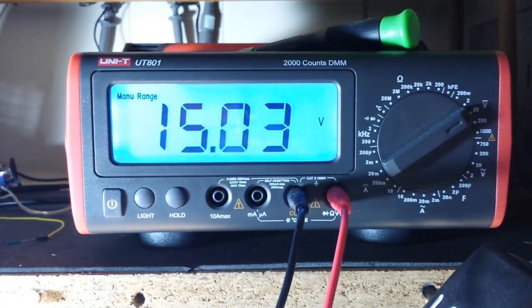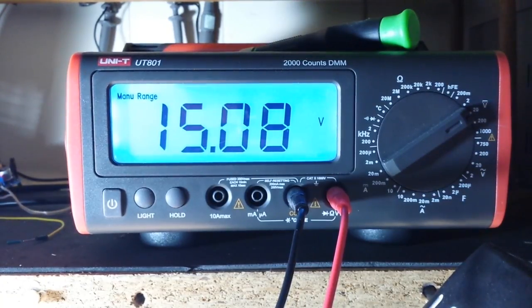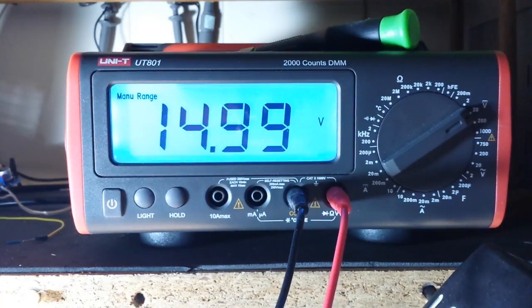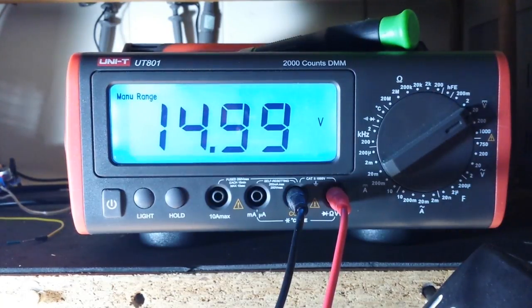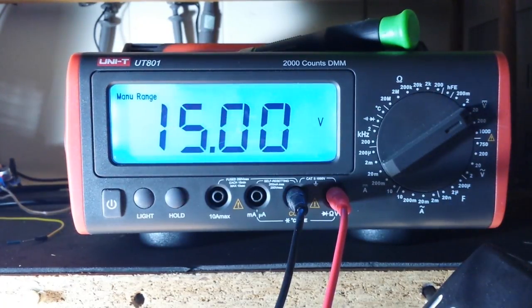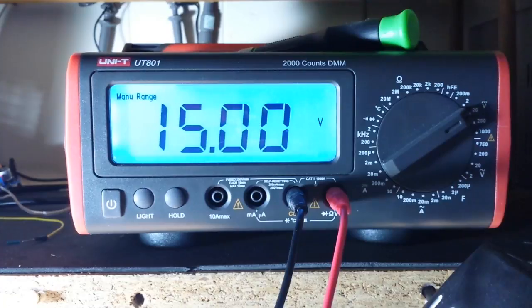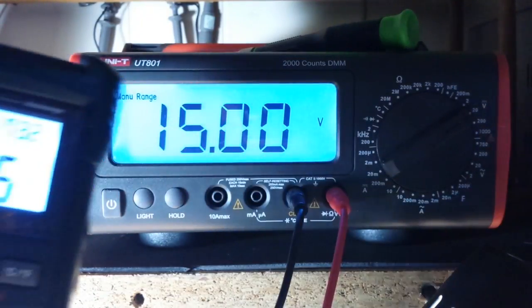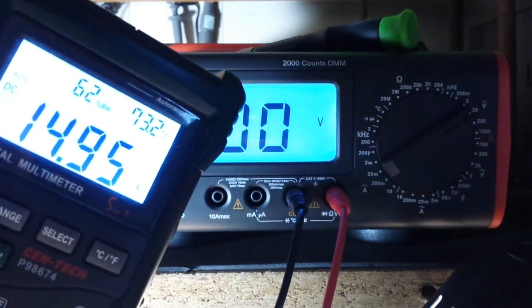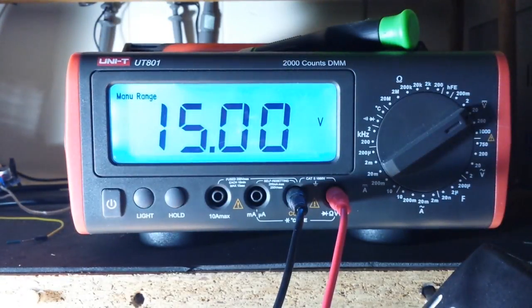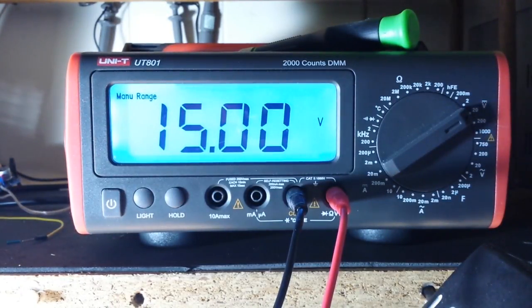Let's see if we get it right on 15. Close enough, so 14, 15 on the UNI-T, 14.95 on the Mastech. It's a little bit off but it's still within the spec.